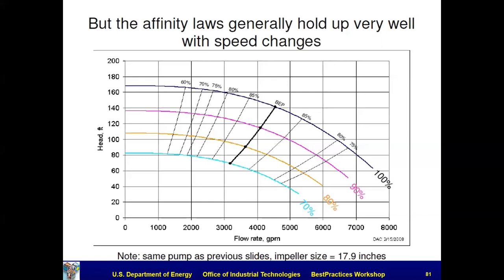And then you put your system curve on there, and wherever that adjusted pump curve crosses your system curve is where you're going to operate. And that's the correct way to do the analysis. So anyway, once you have that, and notice the other thing, so what does BEP stand for?